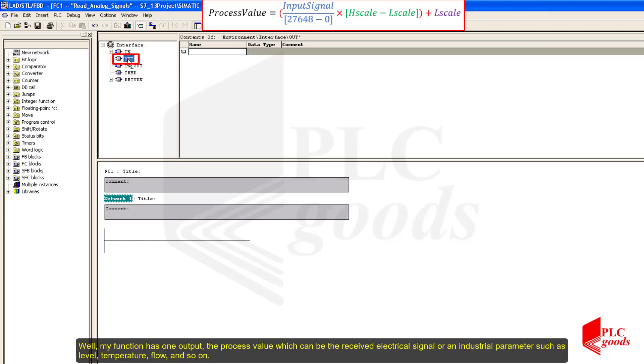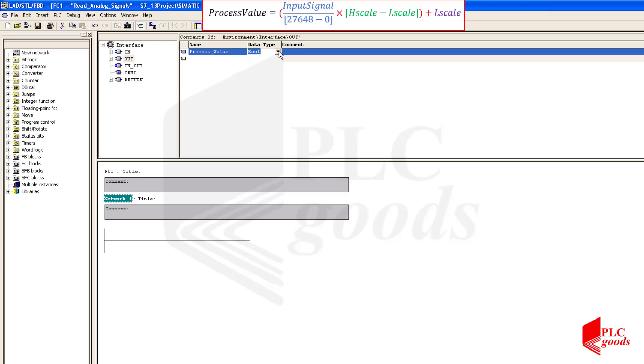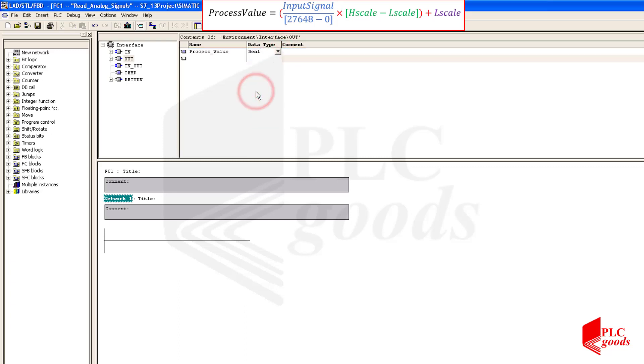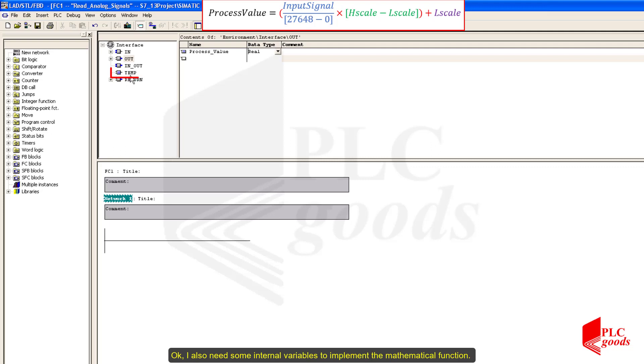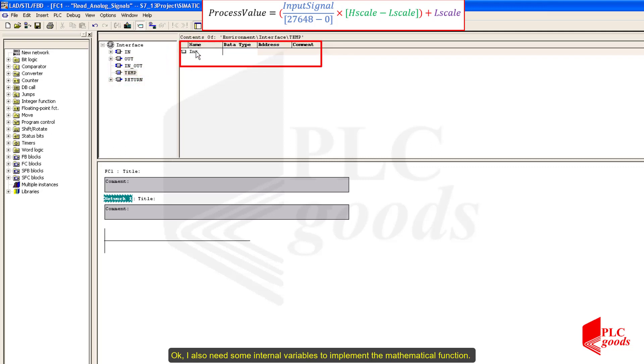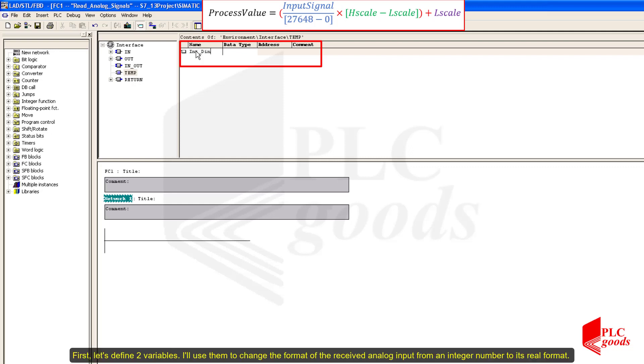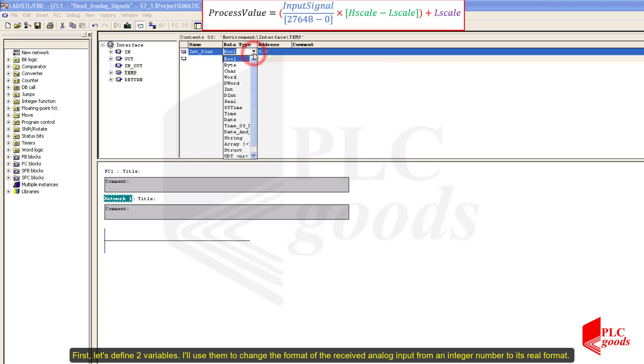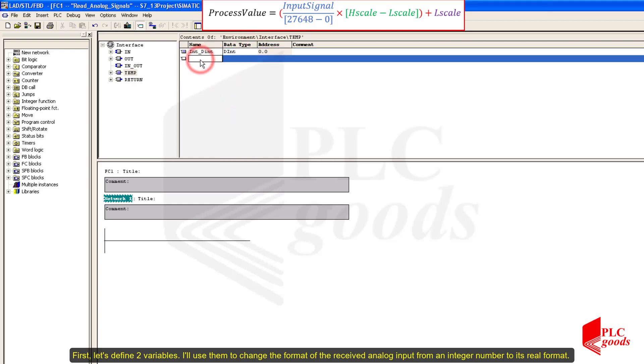My function has one output — the process value — which can be the received electrical signal or an industrial parameter such as level, temperature, flow, and so on. I also need some internal variables to implement the mathematical function. I'll define two variables to change the format of the received analog input from an integer number to its real format.